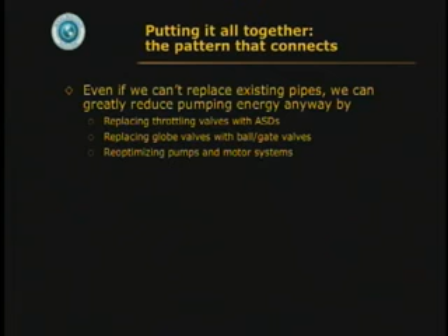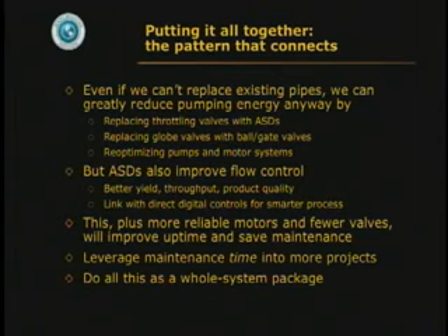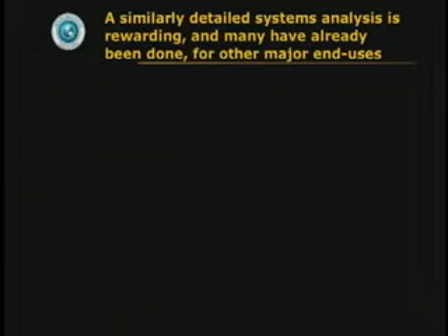Even if you can't replace, say, the pipes in a pumping system, you can replace the throttling valves with adjustable speed drives, get rid of any globe valves, re-optimize pumps and motors, and then you also get better control of your flow. That'll improve your process. You control it digitally. And that plus more reliable motors and fewer valves improves uptime. And then you take the saved maintenance time of your smart maintenance people and leverage it into more projects. Maybe they can clean that heat exchanger nobody's cleaned for 20 years and adjust the controls so things work right. And if you do all this as a whole system package, you get much bigger savings at much lower cost.